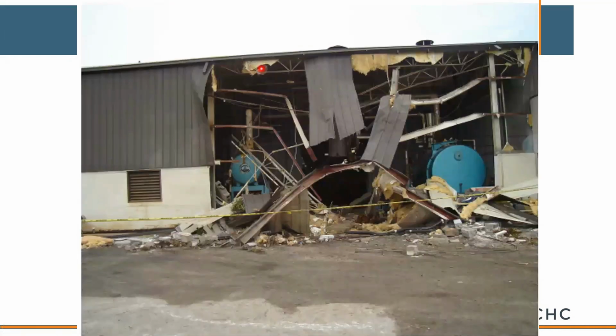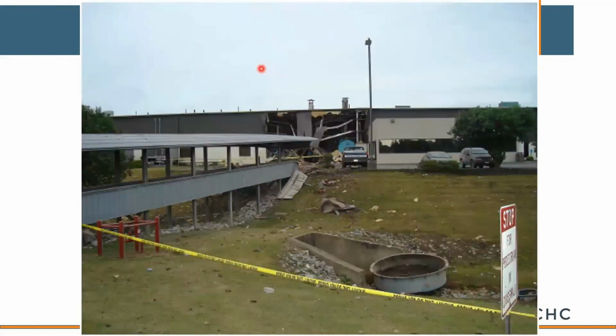Okay, this is the rear of the mechanical room. Obviously, it went boom, and it went big. You can see the rear door for that boiler that flew about 300 feet from the mechanical room. These typically weigh 800 to 1,500 pounds. They're full of refractory or concrete to protect the steel. It took out a car and a walkway on the way to its final resting spot.